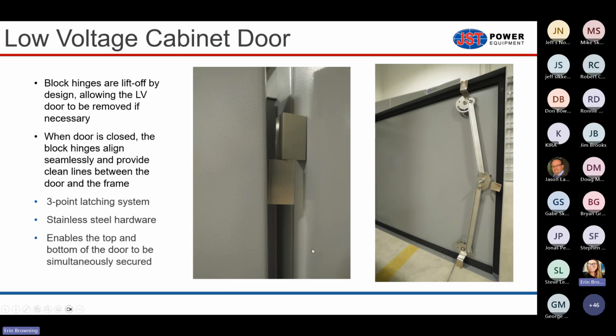The low voltage cabinet door is removable. These are block hinges, and then we have a 3-point stainless steel latching system that's distributed across the top and the bottom. We intentionally angled these inward so that we level out the compression on the gasketing on the top and bottom seams.